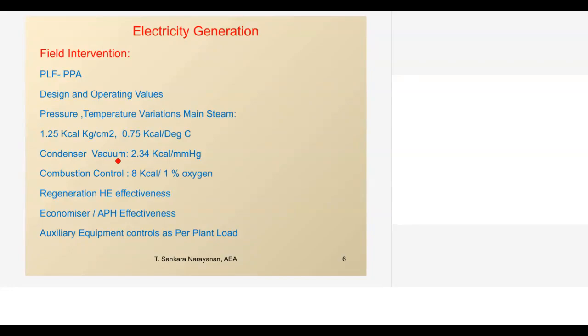Then condenser vacuum, this is a problem irrespective of the size of the plant. Any reduction or change in condenser vacuum will again increase the heat rate. Combustion control, again in a boiler: how is the boiler efficiency we are able to maintain? 8 kilocalorie will be the addition for 1% excess oxygen in the flue gas. Then we also have to review the regeneration, all the HP, LP and IP heaters, and how effective the heaters are. Because sometimes, in operating practice, if there are certain issues, we may bypass certain things. So one has to check how the regenerator effectiveness compares to the design values.